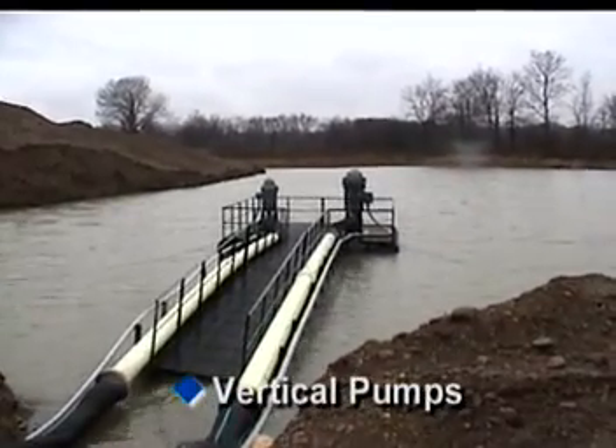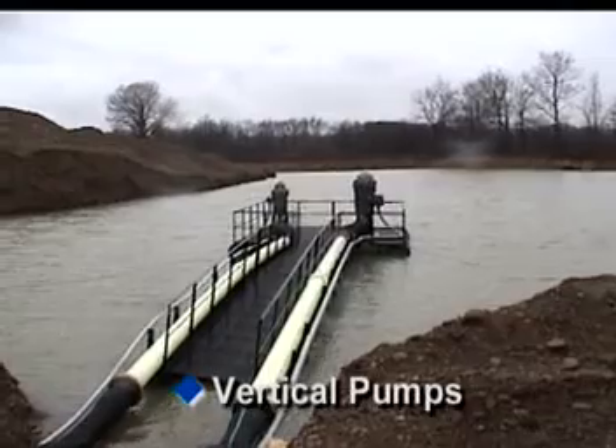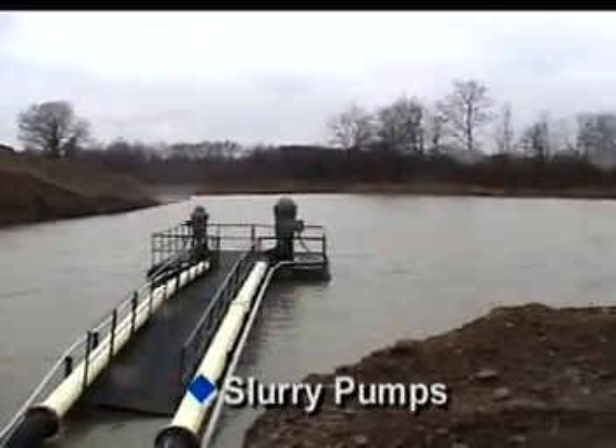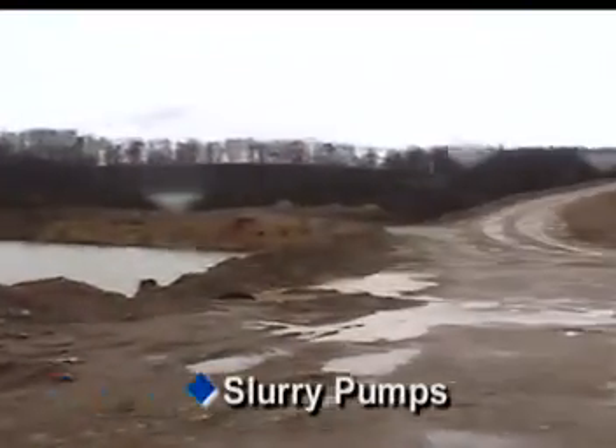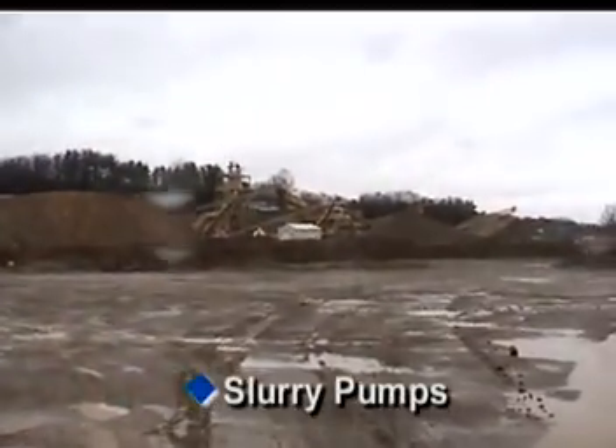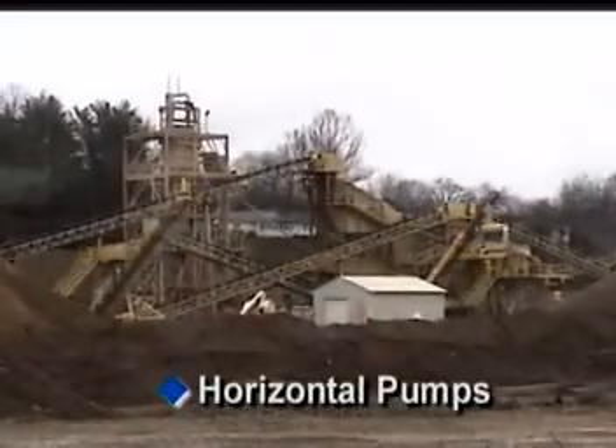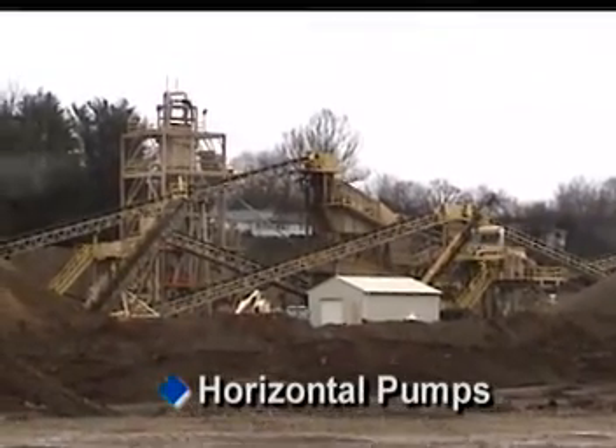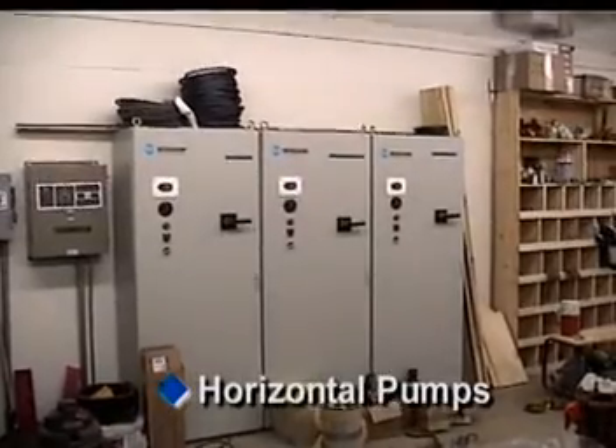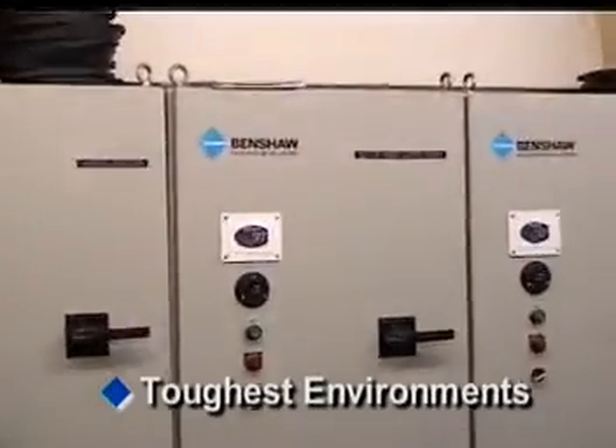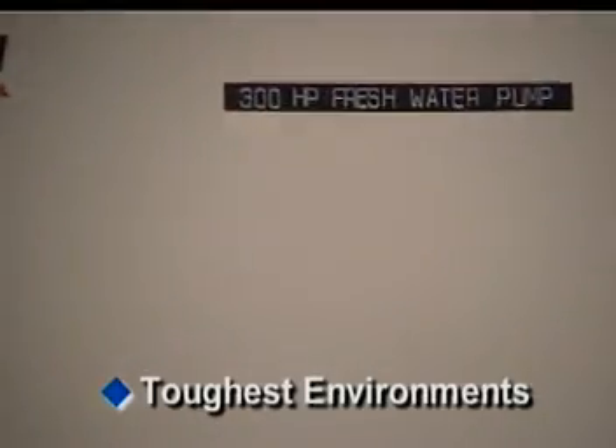Shown here are vertical pumps at a sand and gravel operation. Benshaw's solid-state soft start DMS unit provides a combination main breaker and an NEMA 12 enclosure with external display, customer required operators, and standard adjustable soft start, soft stop. It also provides instantaneous and adjustable over and under current protection for the pump itself.